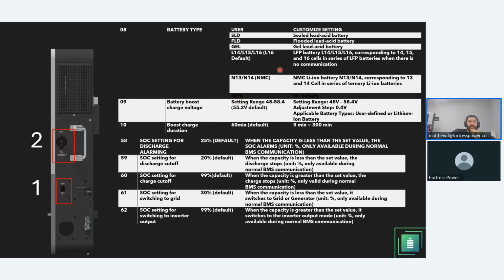You don't have to program any of the voltage settings. You're going to be using SOC, in which here, these are the defaults. The battery cutoff will be set at 20%. Battery setting charge cutoff is at 99%. Well, it's greater than 99%. SOC switching to grid or generator is going to be set at 30%. And then SOC setting for switching to inverter output, so when the battery charges up to whatever you state here, then it's going to go back to inverting mode.